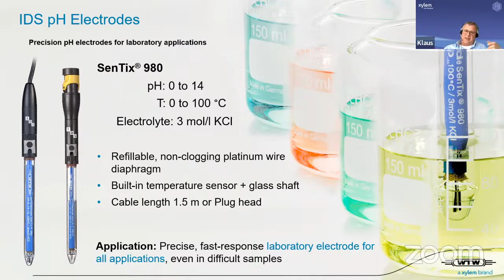Besides these standard electrodes, we have also some special electrodes available, of course, for certain applications. The next one I want to point out is the SenTix 945, and this is an electrode which is really nice because it combines the response time of a SenTix 980 with its fast responding platinum diaphragm with an almost maintenance-free operation. The reason is this electrode has 3 ceramic diaphragms. As I said, you cannot refill the electrode because it's a gel filling, but it's very fast responding, and it's really a nice thing for people who want to save a little bit of work on maintenance of electrodes. So the SenTix 945 is a really excellent electrode for many laboratory applications.